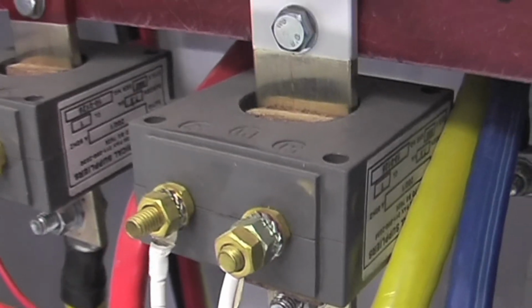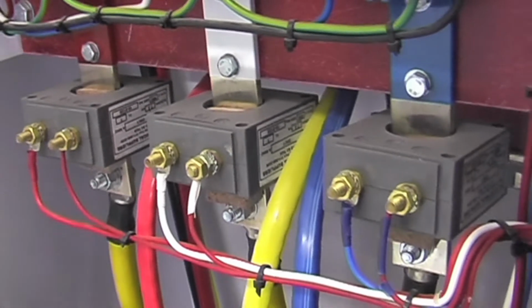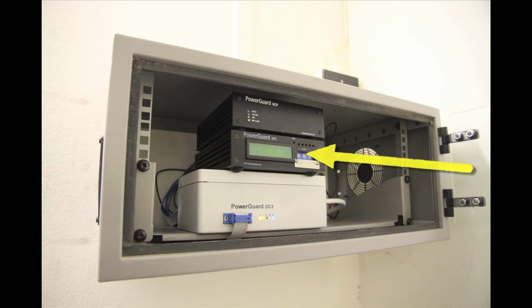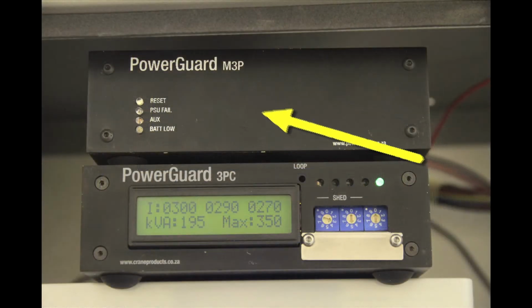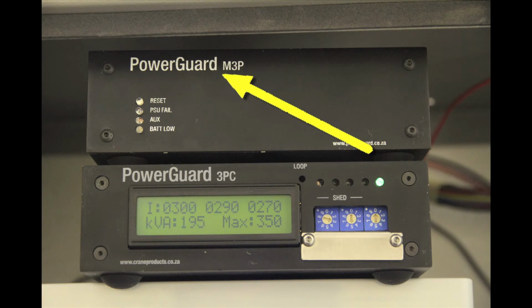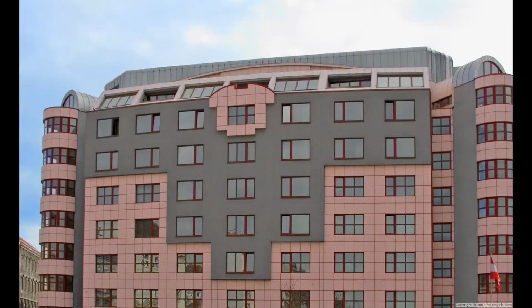In order for you to understand how we arrive at the results we present to you, we'd like to briefly show you our scientific data gathering protocols. High integrity output data from 3 current transformers is applied to the PowerGuard unit, where the real-time kVA is calculated. This information is then presented to a GSM network-based modem, which is in constant communication with our server. For the purpose of this presentation of actual results achieved, we've selected examples of very diverse installations.